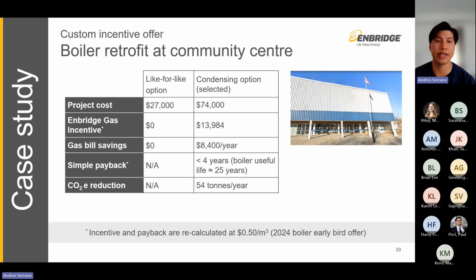You'll see here that had the customer just gone for a like-for-like replacement, the project would have cost them $27,000, but they wouldn't have received an Enbridge Gas incentive. They would not have seen any gas savings on their bills. But because the customer went with the condensing option, which is a more expensive option, they were able to get back $14,000 in incentives and also save $8,400 per year on their bills.